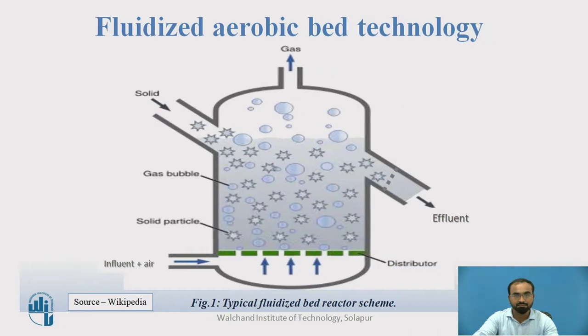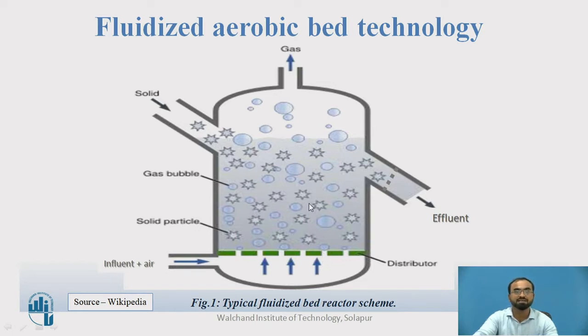Looking at the diagram, you will understand that water including air is made to push inside the reactor. It is typically cylindrical in shape in which the depth is kept much larger than the surface area. As the water is made to push at a velocity which can overcome the gravitational pull, the media will be kept continuously in suspension. As the water passes, whatever organic matter is present in the wastewater will get attached to the media and automatically the biodegradation process takes place.